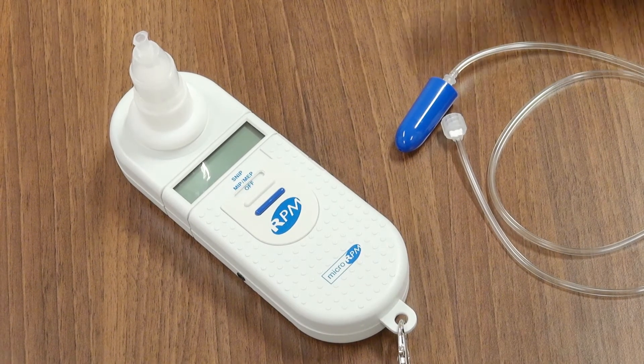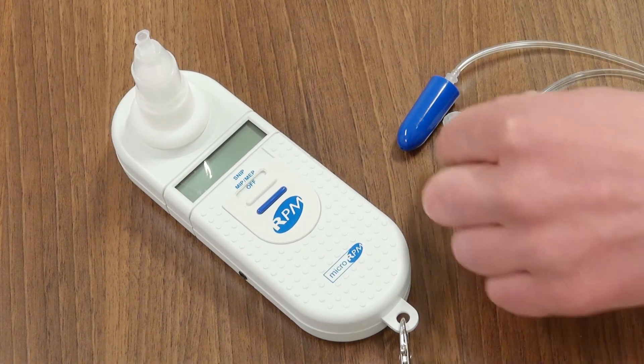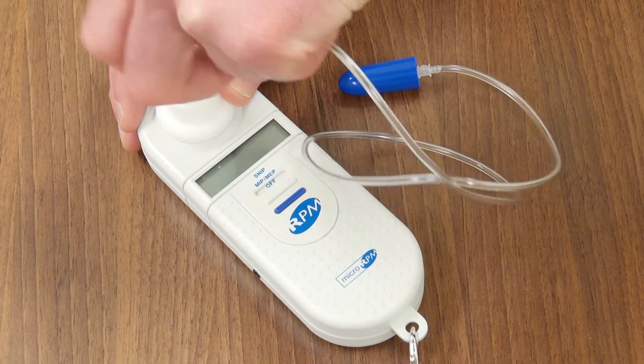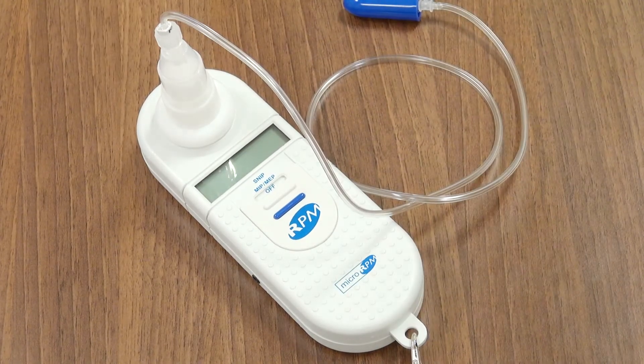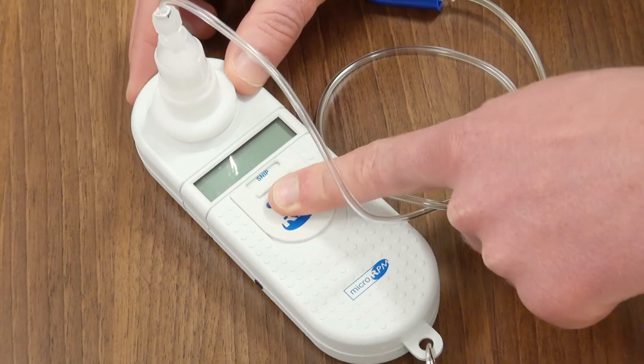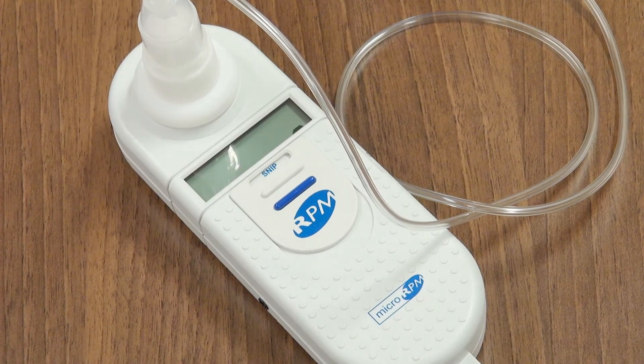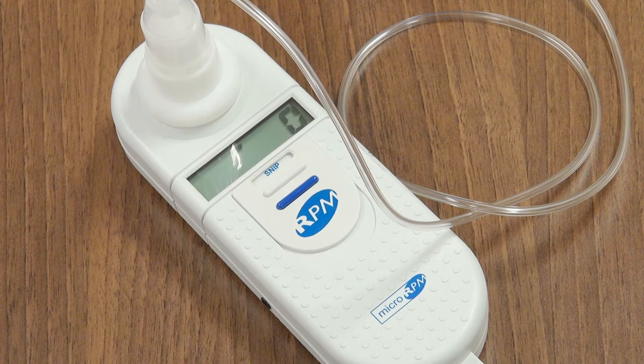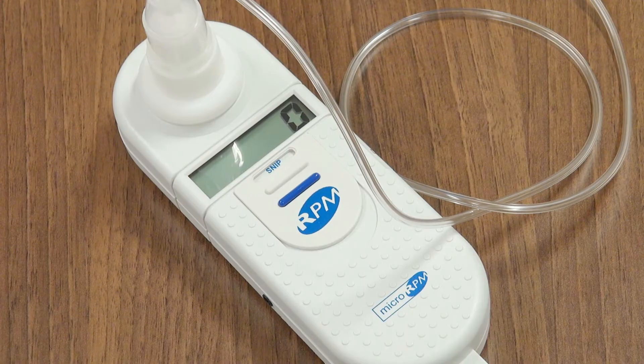Once you have selected the correct nasal probe, attach the nasal probe to the device. Now, switch the device from OFF to SNIP. Wait until the screen of the device shows a zero. Once this is complete, the device is ready for the test to be performed.